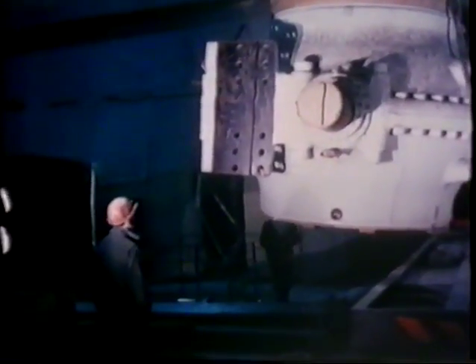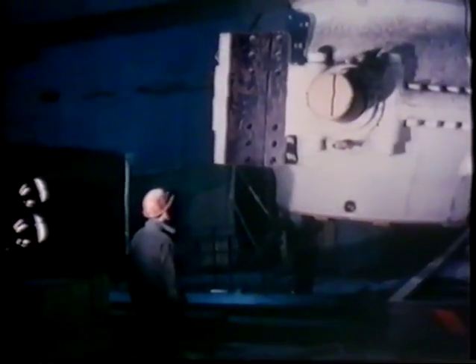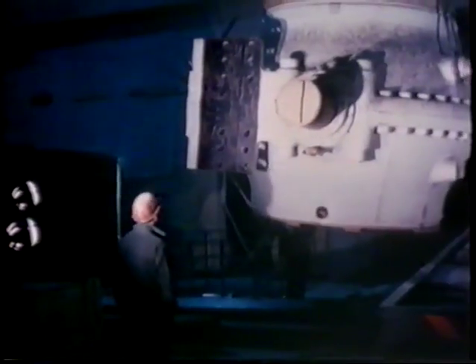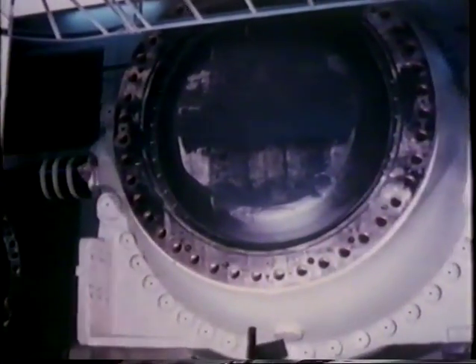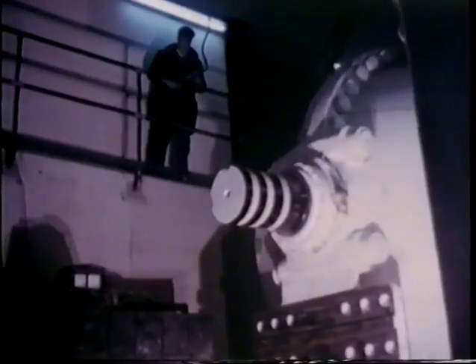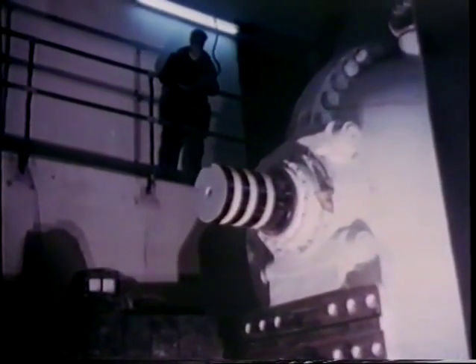High-pressure water entering from the manifold is controlled by spherical valves 1.7 meters in diameter. Each valve is designed to intercept full turbine flow and carry reactions of about 290 tons into its foundations. Together with its operating servo, the valve weighs about 55 tons. A maintenance seal as well as a service seal is fitted so that it is absolutely watertight to allow safe working inside the turbine during overhauls.